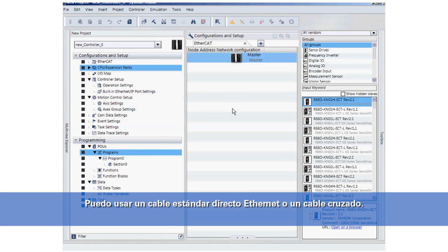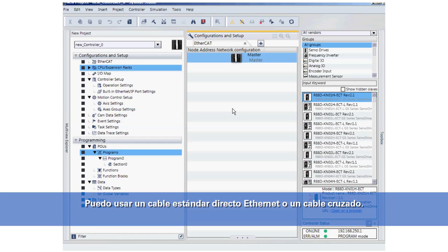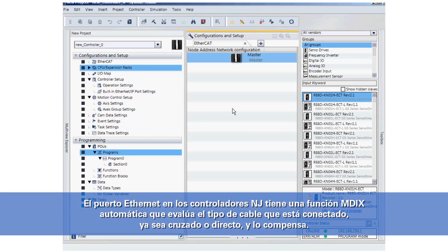I can use either a standard straight-through Ethernet cable or a crossover cable. The Ethernet port on our NJ controllers has an AutoMDIX function which looks at the type of cable that is connected, whether it's crossover or straight-through, and compensates for it.